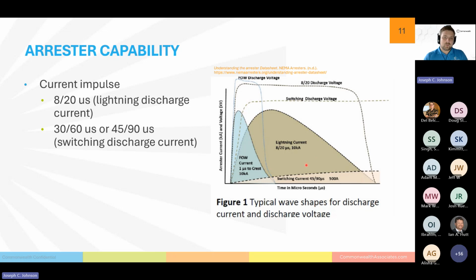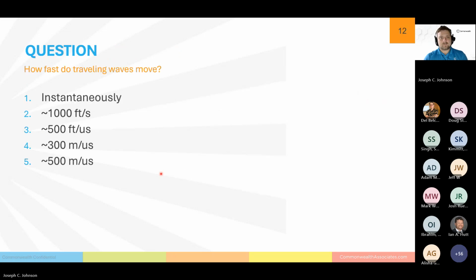An important note, and we'll get into this later, these waves are also associated with current values, and we'll get into those when we get into arrester data sheets. These are basically a magnitude of the current coming in on that wave. Generally, we try to size it for the most conservative. This can go anywhere from 5 to 40 kA, and for switching 500 to 1,000, 2,000 amps. So another question, how fast do traveling waves move?